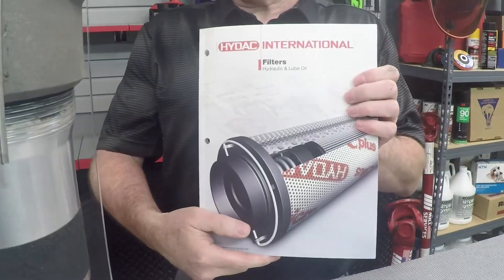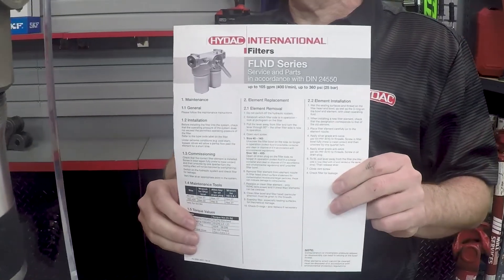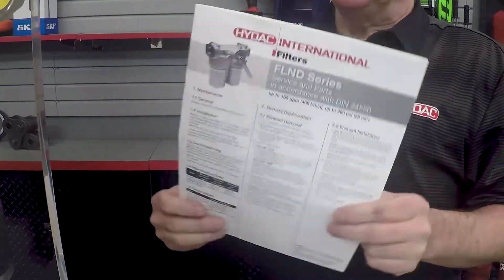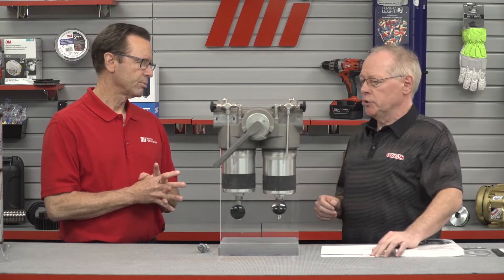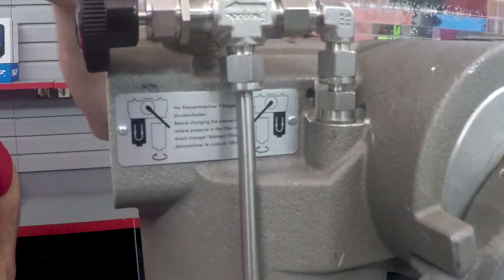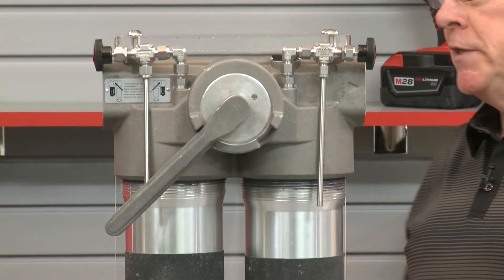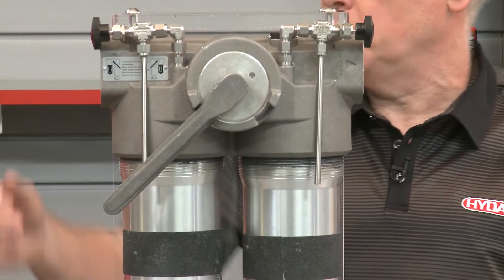Be ready to refer to your catalog page for the filter, and also look at the service manual, because you need to know the required tools and torque values for your particular filter. To determine which side is operational, look at the pictogram on the front — that will tell you exactly which of the bowls is operational at this point in time. The lever will point to the side that is not in use.